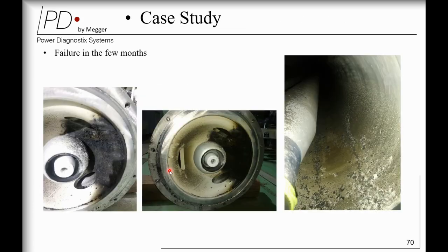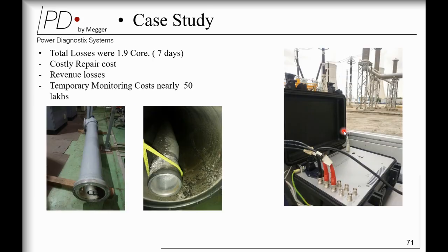And just after a few months, we suggested to the customer to do the trending and monitoring, because earlier they also had a few failures in the compartment. But unfortunately, after a few months, the customer had not taken action on the GIS, and you can see the image is self-explanatory of what happened in the complete GIS system. So this was very costly.